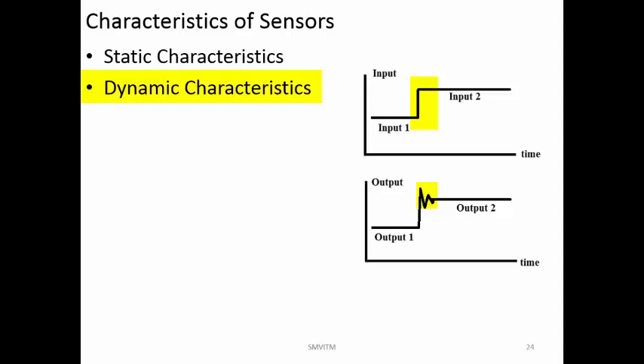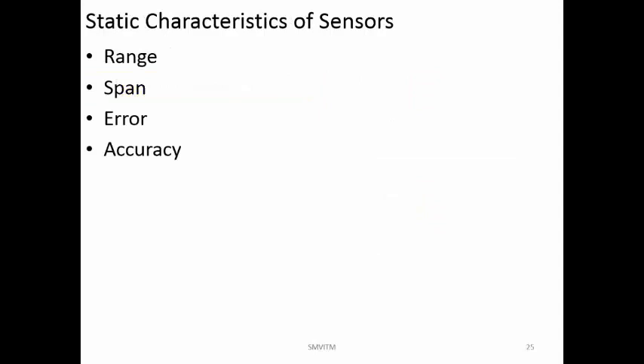So first we will be discussing the static characteristics. Among the static characteristics, the first one is the range. The range of a transducer, sensor or measuring instrument is the values in which you can use a particular instrument or device. So a sensor may have a range of say 0 to 100 degrees centigrade if it is a thermometer, or 0 to 25 volts if it is a voltmeter. If it is a force measuring device, it may be say from 50 to 500 kilonewtons. Like that, it will have a certain range.